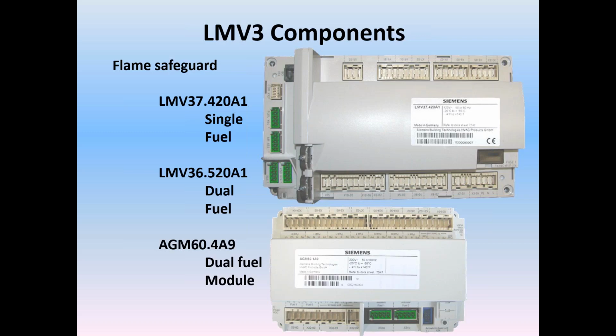is a safety-related, so-called force guided relay that switches from the gas settings to the oil settings, or from propane to natural, two different gases, two different curves. And it's a safety-related relay that does automatic switchover. All you do is change fuels. It cycles down on one fuel, switches over to the other fuel, and brings it up on the second fuel at the push of a switch, so it does automatic sequencing of fuel change.